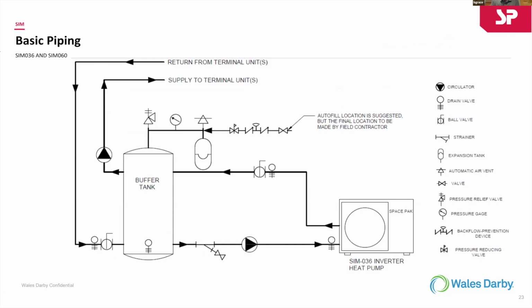So this is a pencil drawing of what you're looking at. You've got your unit outside. We've got a circulator that takes the water and sends it in and out of the buffer tank. The buffer tank basically replaces what was the boiler in the house. So all the piping to the buffer tank in a hydronic system is the same as if you were piping it to a boiler. You have your expansion tank, your feed valve, and then you have your piping off of it.